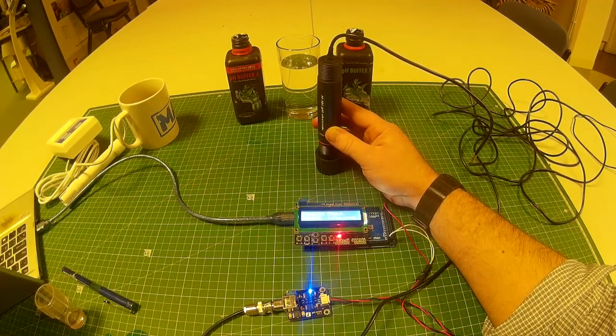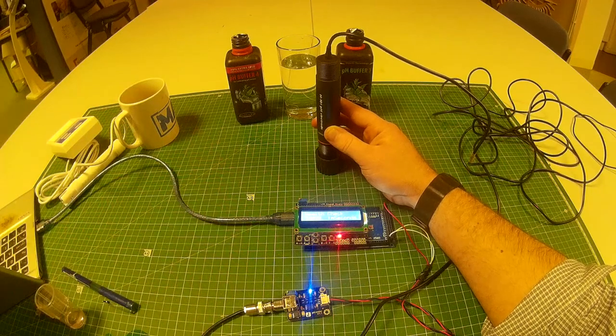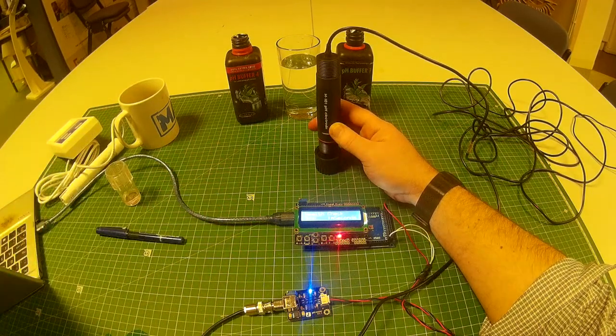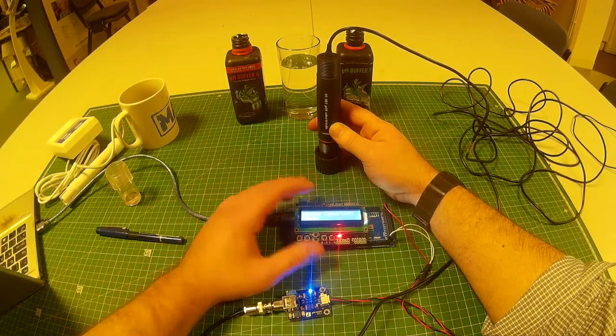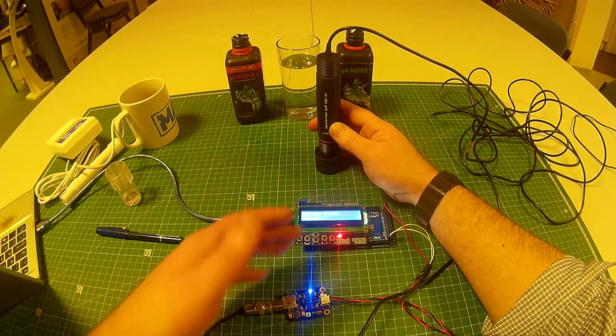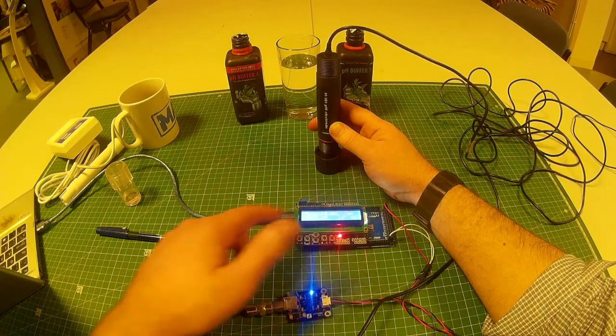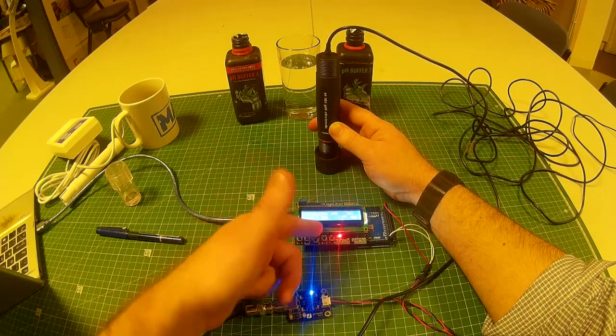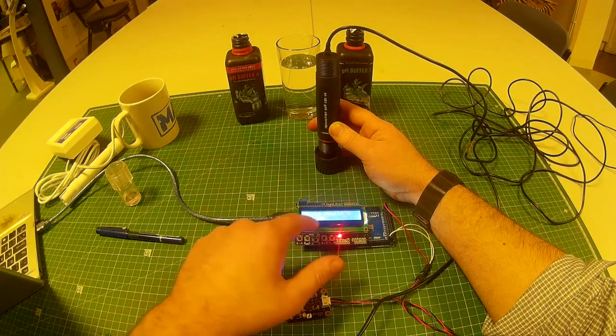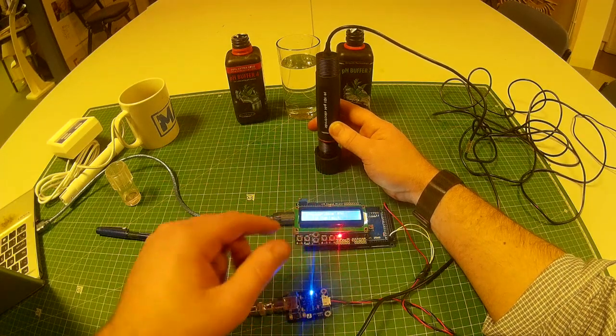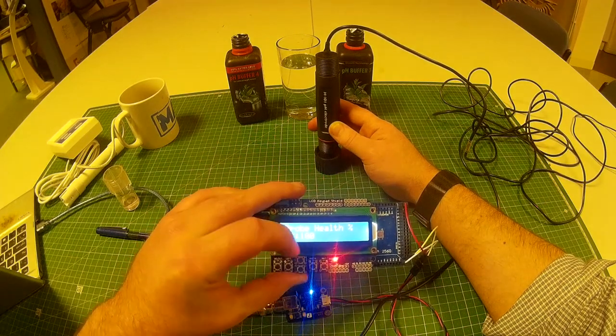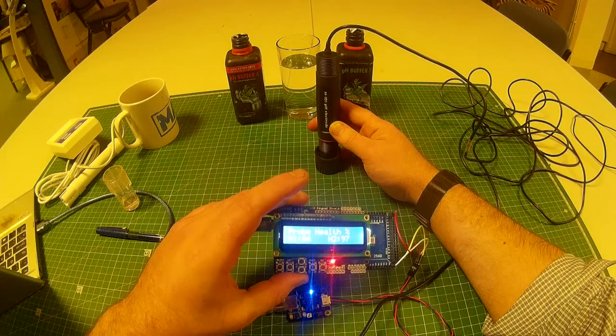So now it's finished the calibration, it's just checking the health of the probe. So I'll cut the video back in 60 seconds. And we're back. So it's saying the probe condition's good. If it wasn't it would say bad. So press right to exit. That pH is 4. Let's click back up to the probe health. 100%, 84 and 97.